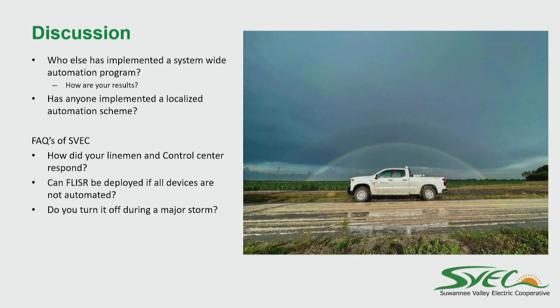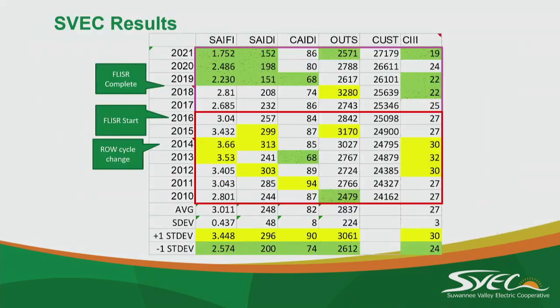A couple questions on your indices. Your major event day, is that more than 90% of your coverage area? A major event day is defined by IEEE standard. There's an equation that looks at your 5-year running SAIDI average, and it creates an annual threshold basically. Ours, I think when we started this was up around 35 minutes in one day would be considered a major event day. And now I think we're down in the low 20s because our SAIDI has been coming down.